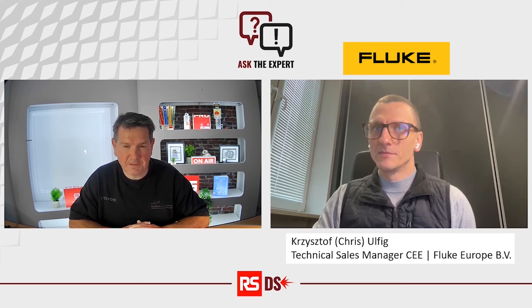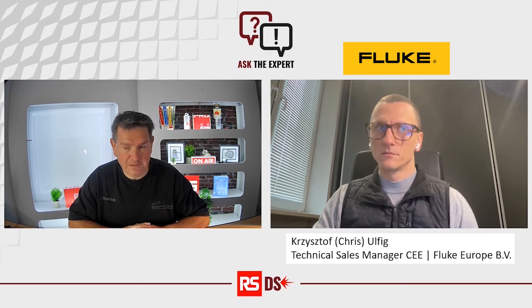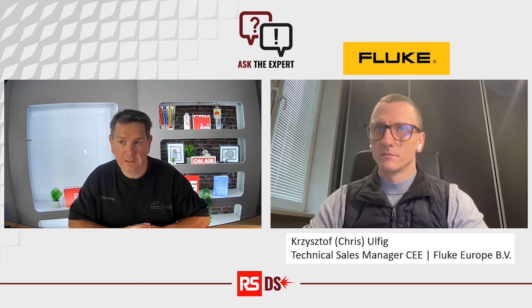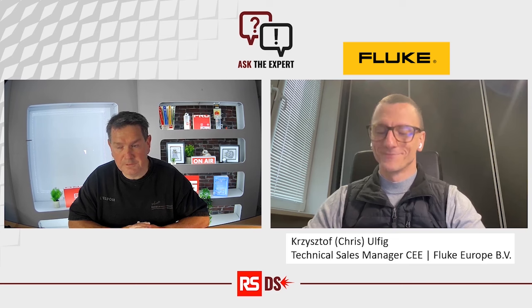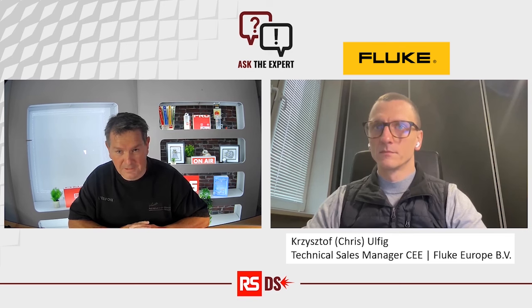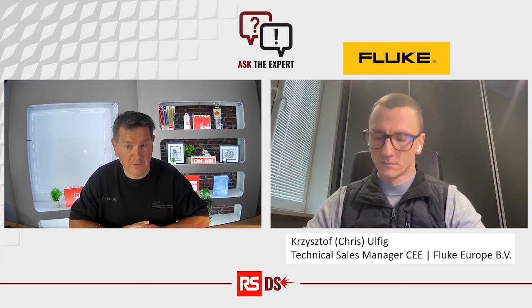They sound absolutely fantastic. And when I was saying that these are so well thought out, the last two examples you gave about the testing before you actually go on to measure installations, for the proving unit, that to me reminds me of some of the things that I used to get taught when I was first starting out in this industry. Number one, always check your test leads. Make sure there's no breaks, because your test leads are your link between you, the meter, and the circuit. The proving unit idea, we can put a link to more information about that, but I wasn't actually aware of the zero when you were talking about the other option.